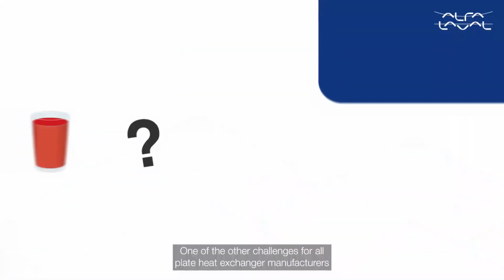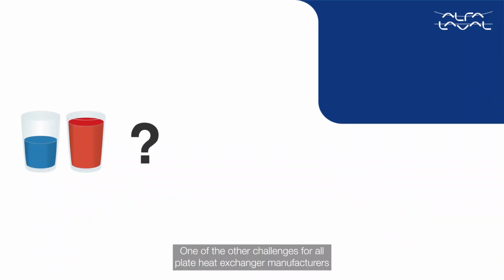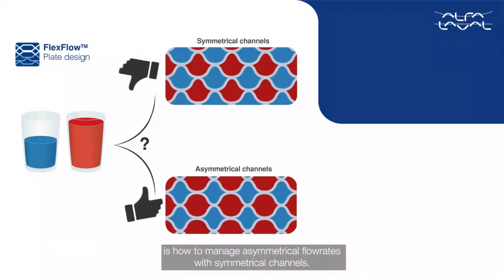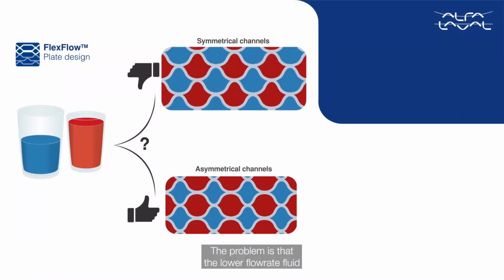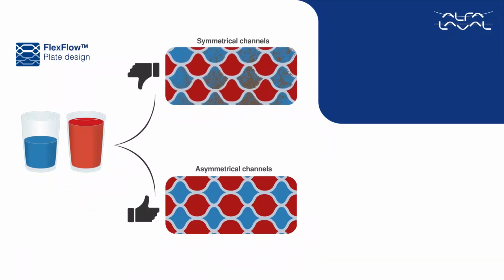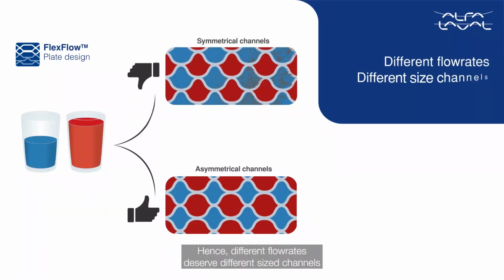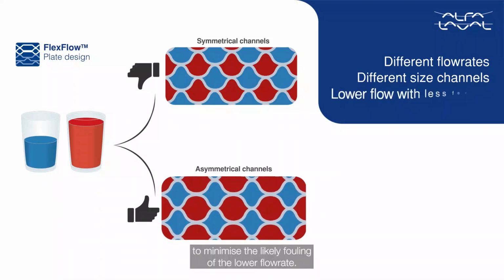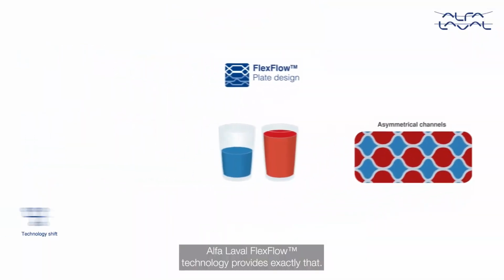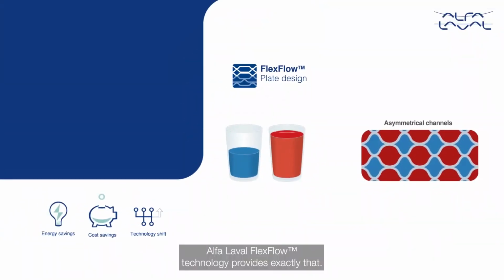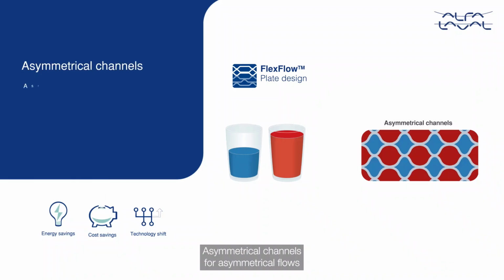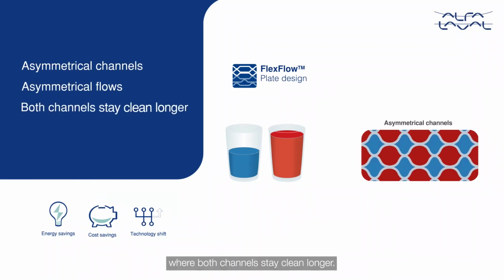One of the other challenges for all plate heat exchanger manufacturers is how to manage asymmetrical flow rates with symmetrical channels. The problem is that the lower flow rate fluid will start fouling due to lower velocities. Hence, different flow rates deserve different size channels to minimize the likely fouling of the lower flow rate. Alfa Laval FlexFlow technology provides exactly that. Asymmetrical channels for asymmetrical flows, where both channels stay clean longer.